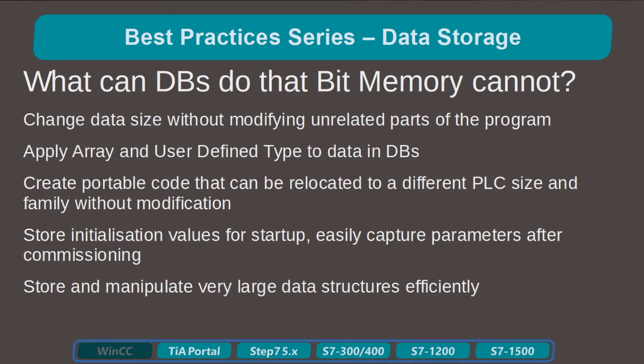We can store initialization values for startup. It's easy to capture parameters after commissioning, so that you can start up your DBs with default parameters which you don't need to set anywhere in your program. It's set on startup and done. And another good reason is you can store and manipulate very large data structures very efficiently using DBs, either moving a whole DB around or moving data around using user-defined types or aggregate types.